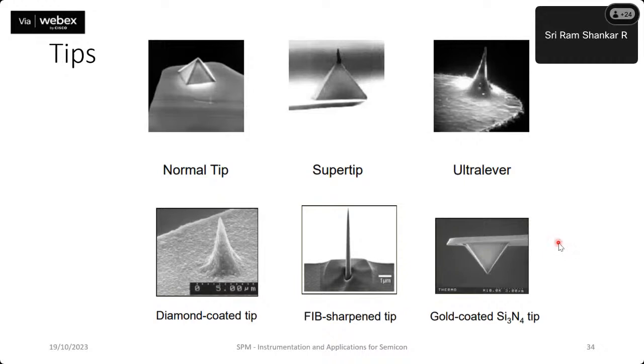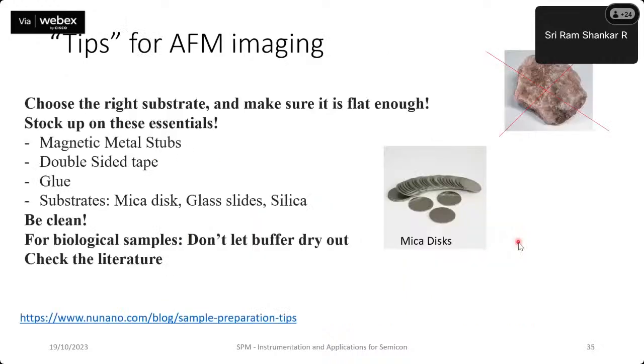For conductive applications where you want to measure electric forces, you would need to use a gold-coated tip, which is also conducting with respect to the sample. So these are some tips for AFM imaging.